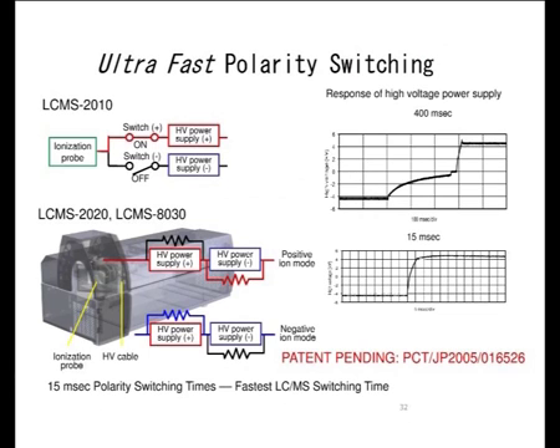I am now going to polarity switching. This is also one of the important functions when you deal with ions having different polarity. When compounds get ionized, some get ionized in the positive form, and some in the negative form. When you analyze the positive ions, all the voltages from the start until detection are set so that all the positive ions get separated. When you want to analyze the negative compounds, the voltage switches over from positive to negative. The switch over time is known as the polarity switching time. If the polarity switching time is very slow, what happens? During the switching time, most of the ions get lost, and because of that the quality of the data is reduced.